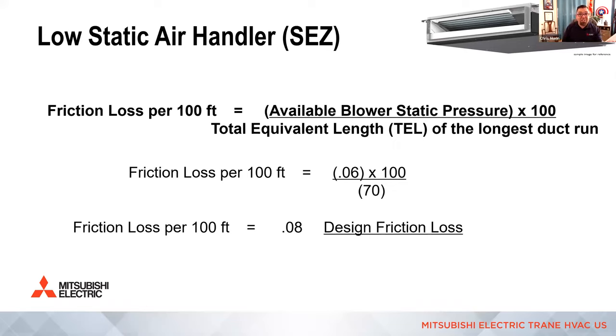And we see this a lot actually with ducted heat pumps. And I'll show you that when we get to the higher static air handlers, because everything's part of the system shipped with the blower. So we tend to have more static to go around than we need, all right? Or increase the TEL, maybe use a couple bad fittings to slow the airflow down. Otherwise it becomes noisy, okay? So they give you the guidance right on there.